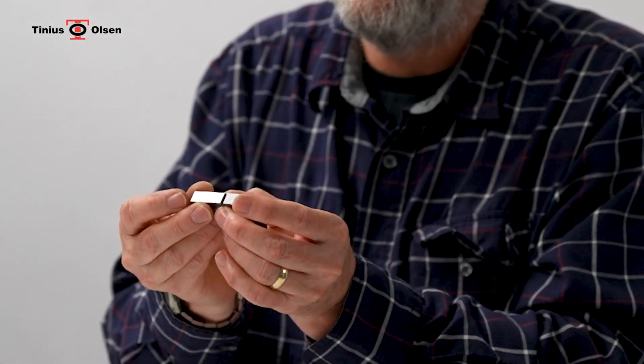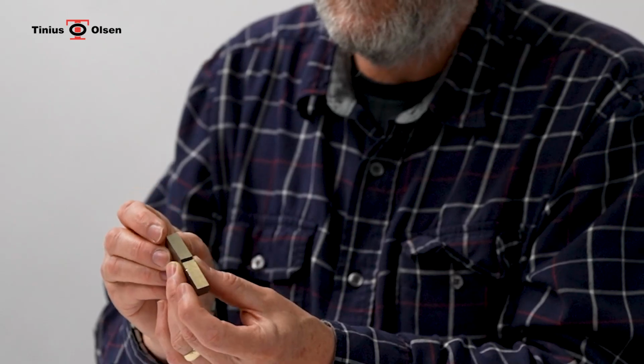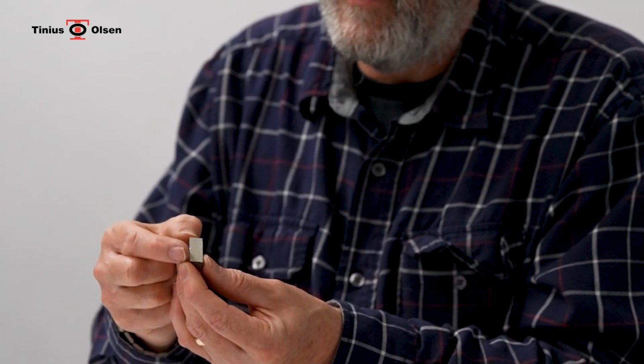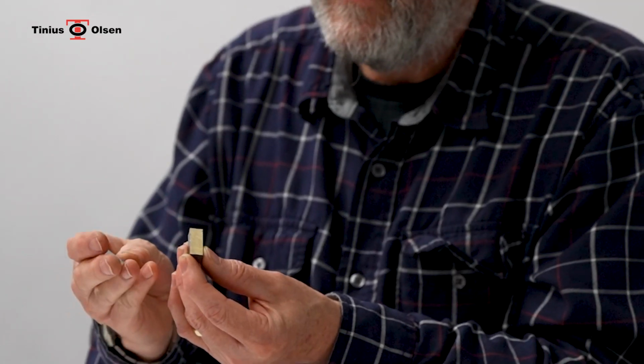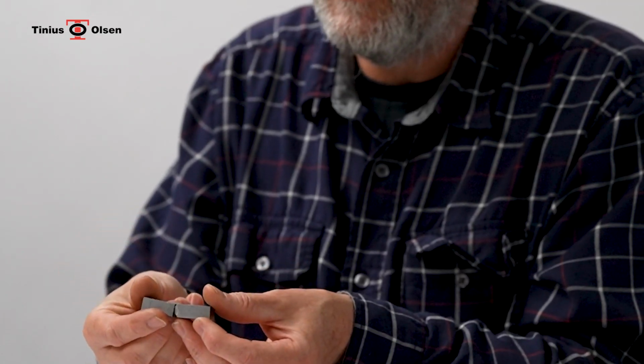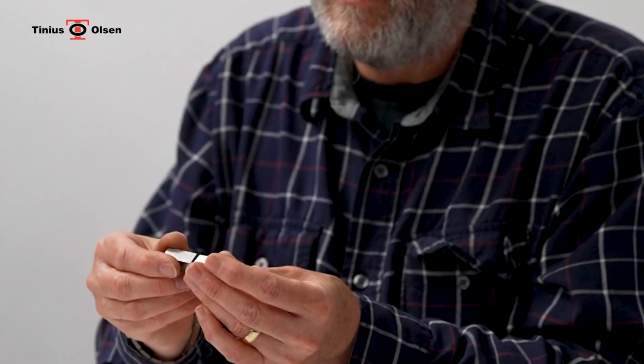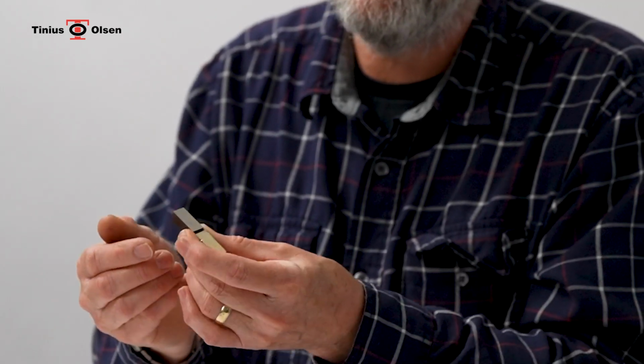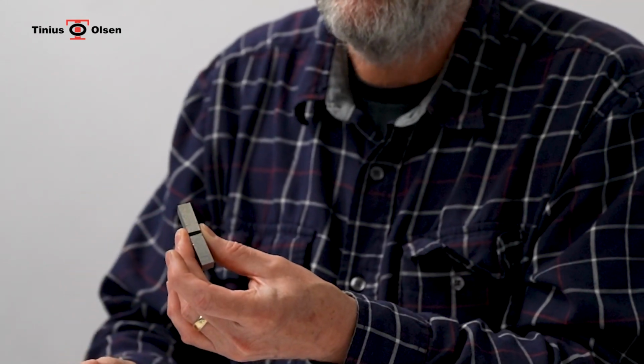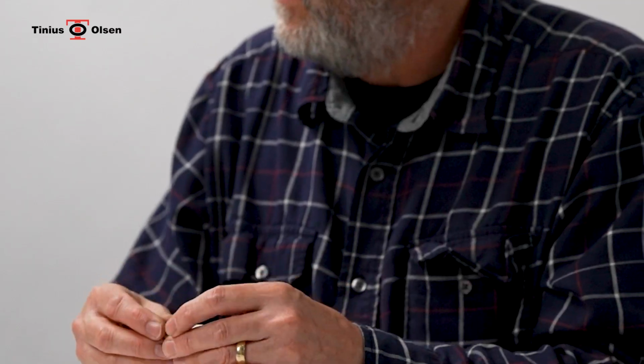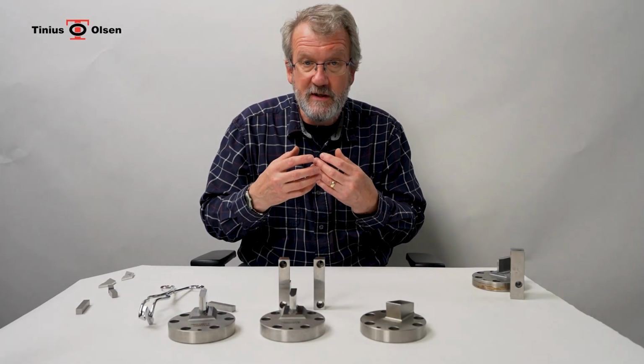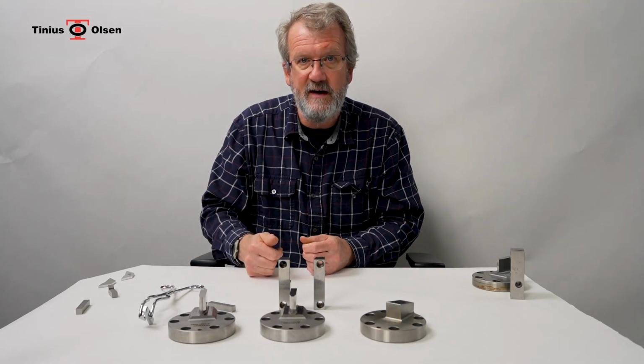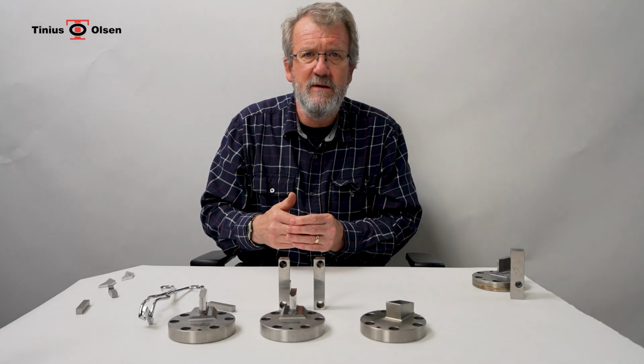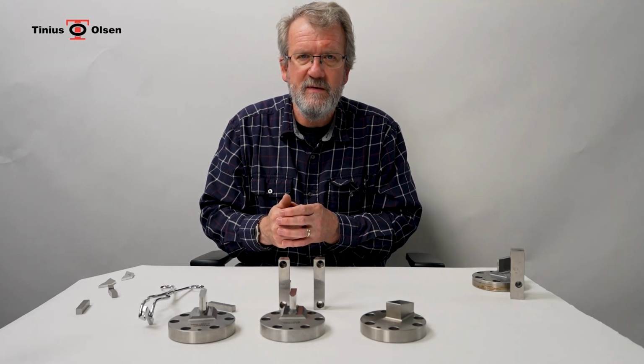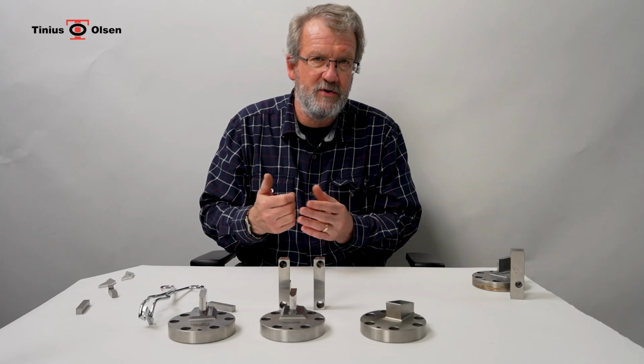NIST also examine the samples to see if there are signs of wear or damage on either the anvils or the striker. This is a sample I have previously broken, and there are witness marks to show where it actually struck the anvil and where the striker was. Now, it is not easy to see on this sample where the anvils were, but if those anvils were in poor condition, they would smear and they would leave marks on the sample indicating wear. Although NIST cannot actually measure the samples, because the survey they send out with the material is, does the machine meet the requirements, they will actually recommend that anvils be addressed or the striker may need to be recentered.